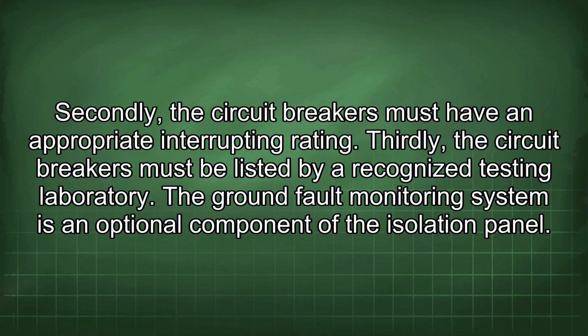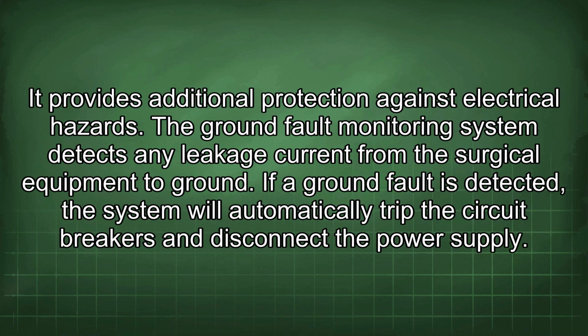Thirdly, the circuit breakers must be listed by a recognized testing laboratory. The ground fault monitoring system is an optional component of the isolation panel. It provides additional protection against electrical hazards. The ground fault monitoring system detects any leakage current from the surgical equipment to ground. If a ground fault is detected, the system will automatically trip the circuit breakers and disconnect the power supply.